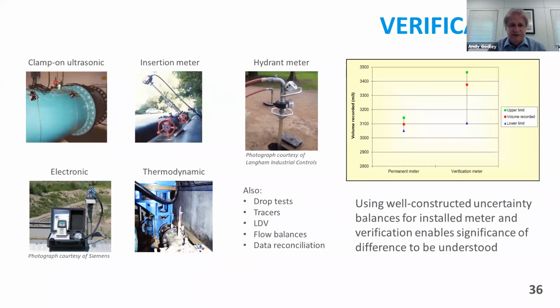So we have a number of different ways of verifying meters, whether that's through doing independent flow tests, through something like a clamp-on ultrasonic, which Michael's talked about, an insertion meter, or other more advanced methods like thermodynamic testing, where you've got a pumped flow, tracer methods, and so on. So lots of different methods. Also, the electromagnetic meter manufacturers, particularly Siemens and ABB, provide us with electronic verification tools, which I understand are quite well used in the UK, but perhaps less used in other parts of the world.